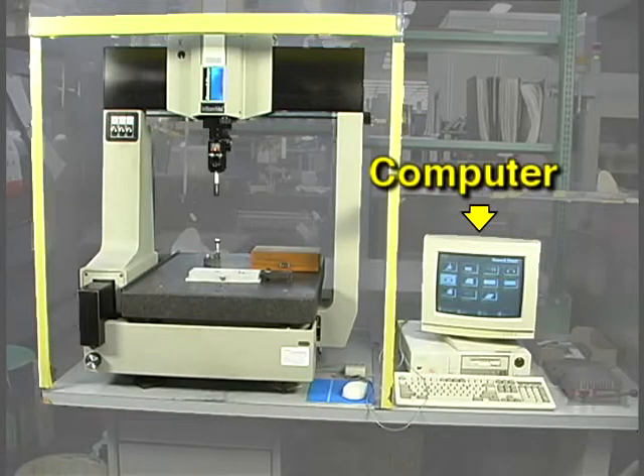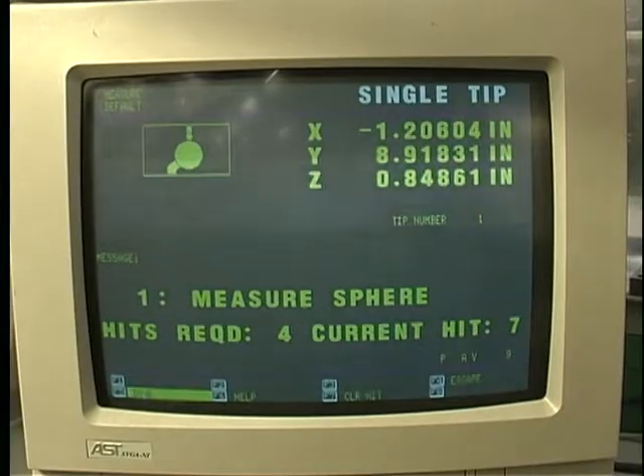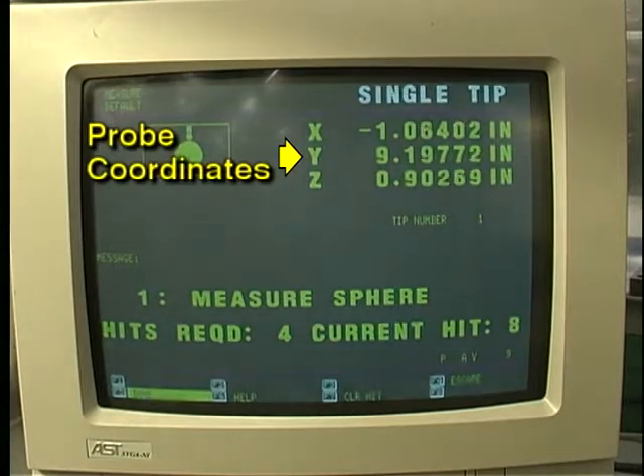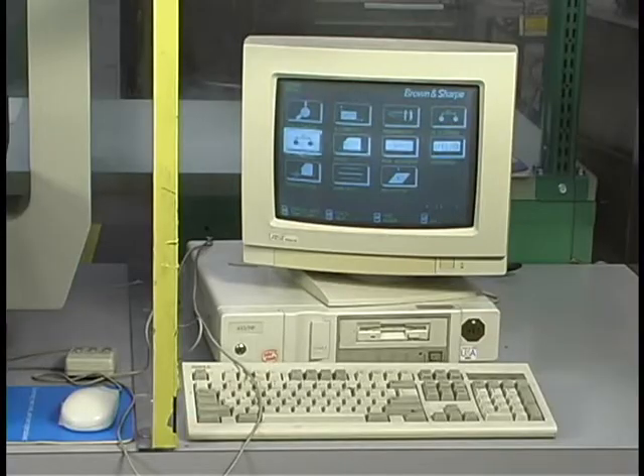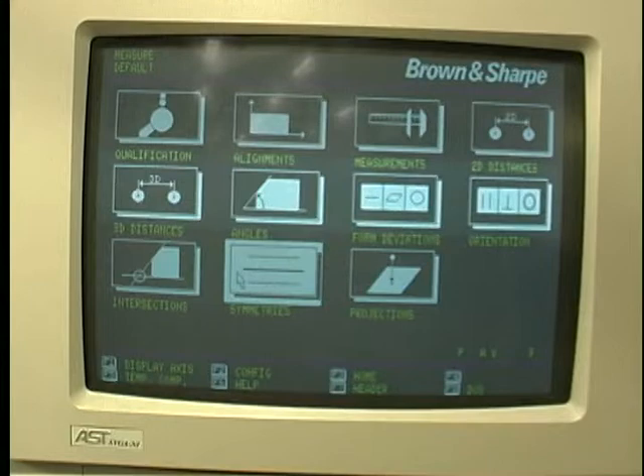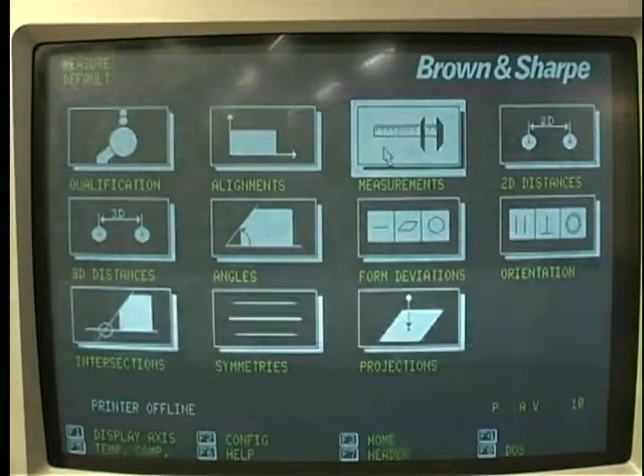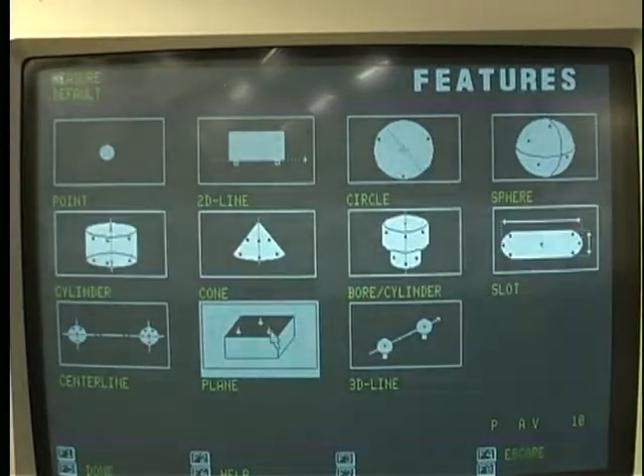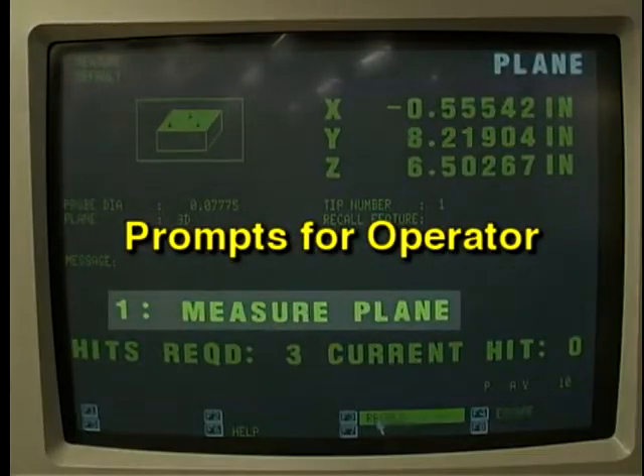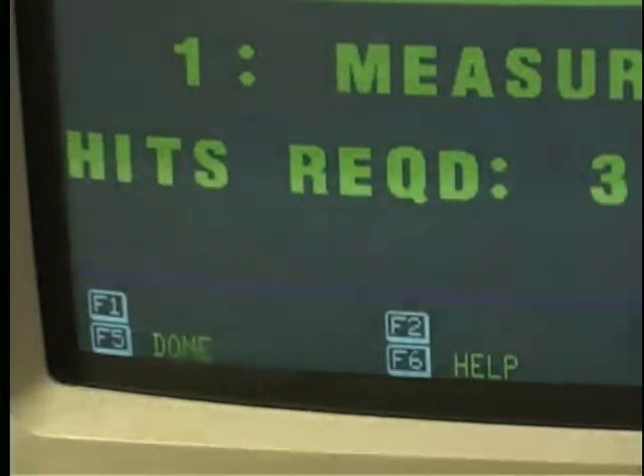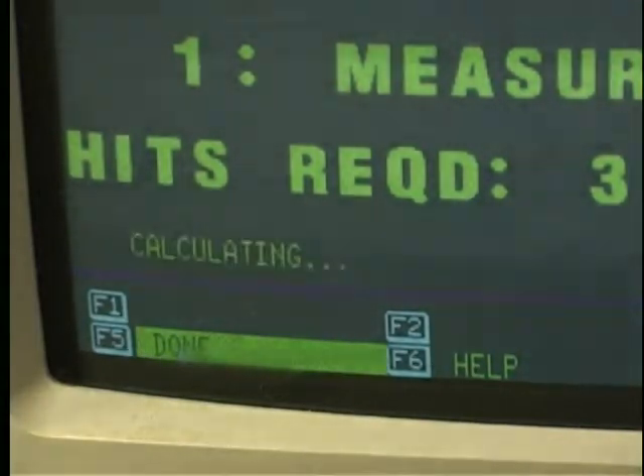This CMM has a computer connected to it. As the probe is moved, the coordinates of the probe tip are displayed by the computer. The computer is a normal PC which is using special software designed for use with this CMM and probe. The software includes a series of measuring procedures indicated by icons on the screen. Once a procedure is selected by clicking on an icon, the software will prompt the operator to perform each step required to complete the measurement procedure. The computer will then store all the measurements and calculate various values when needed.